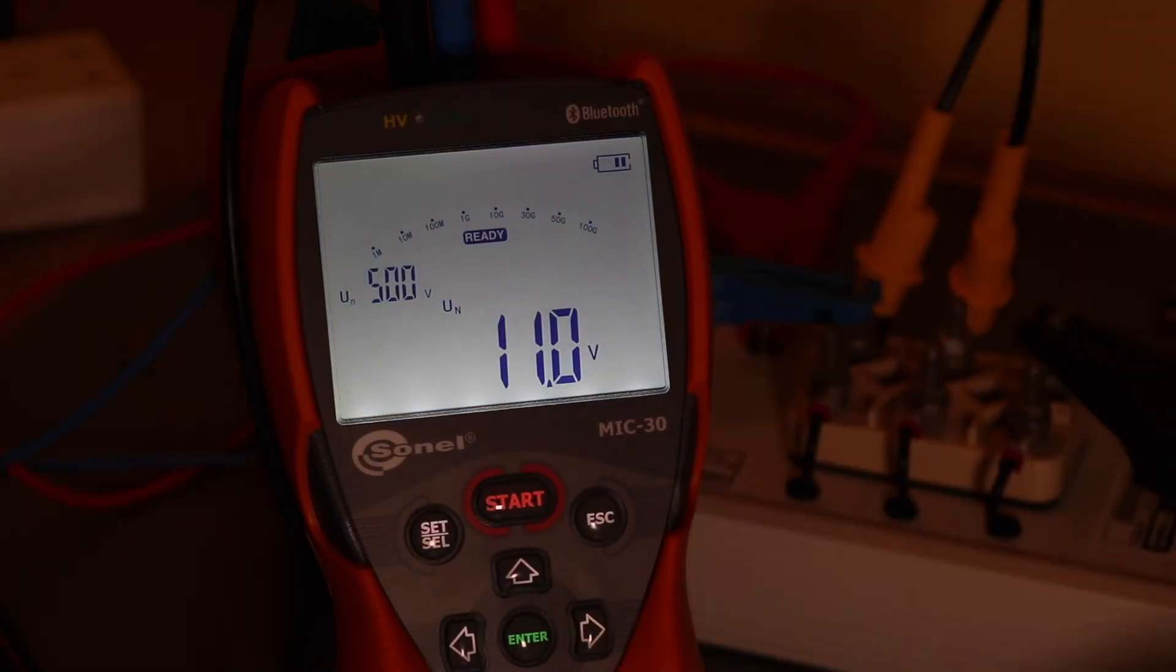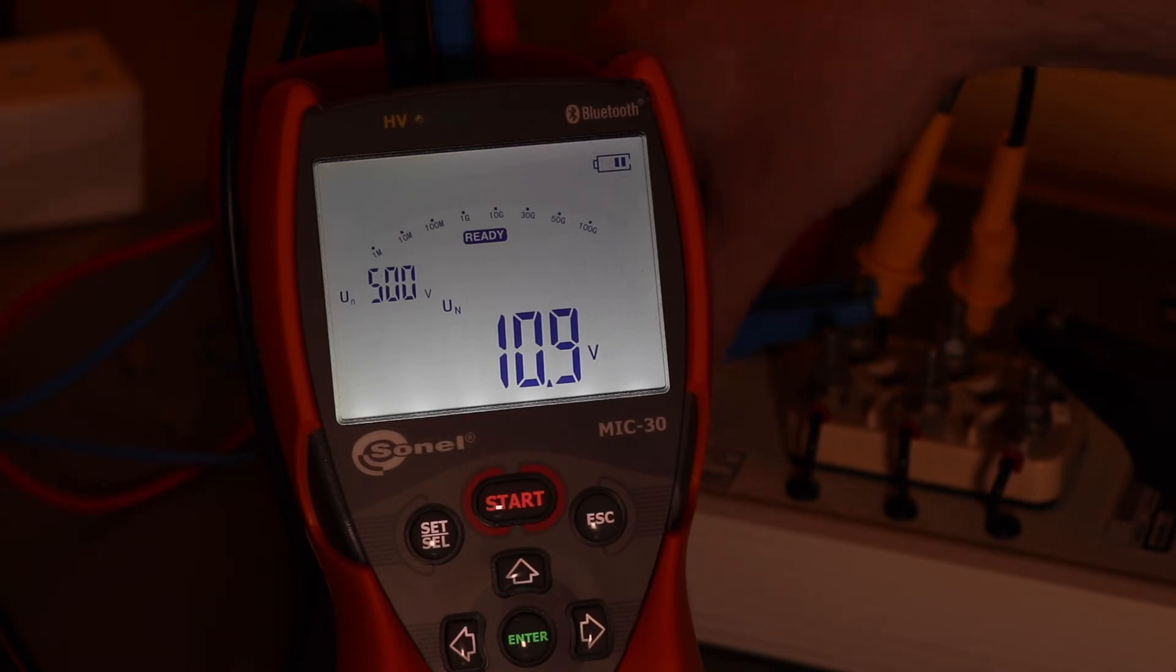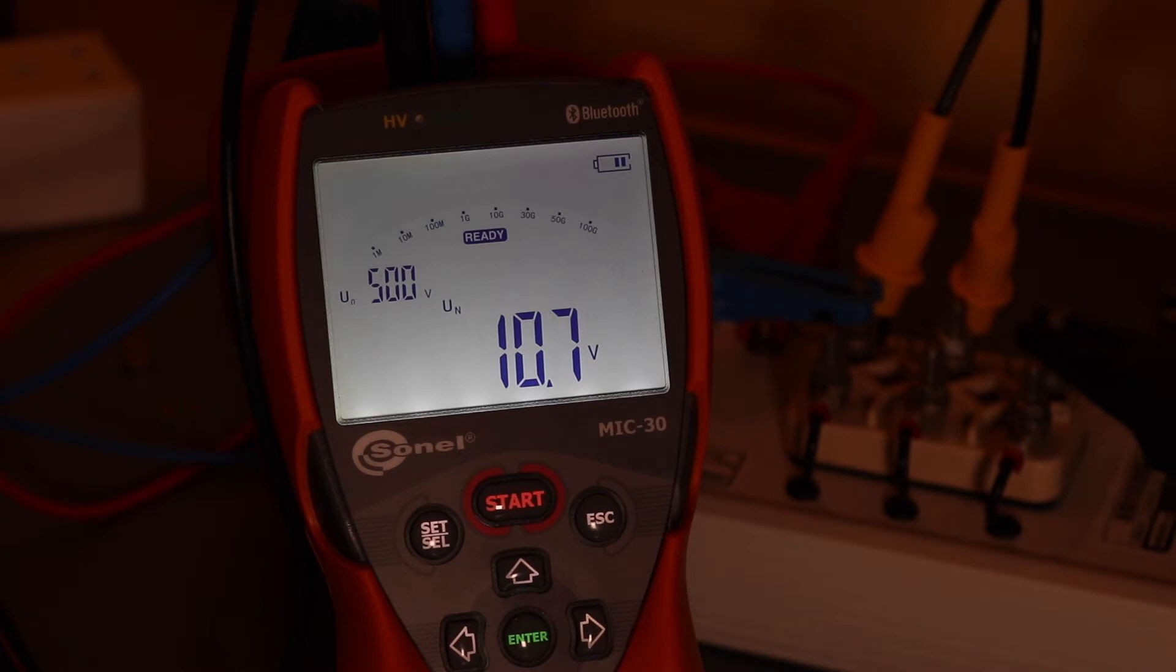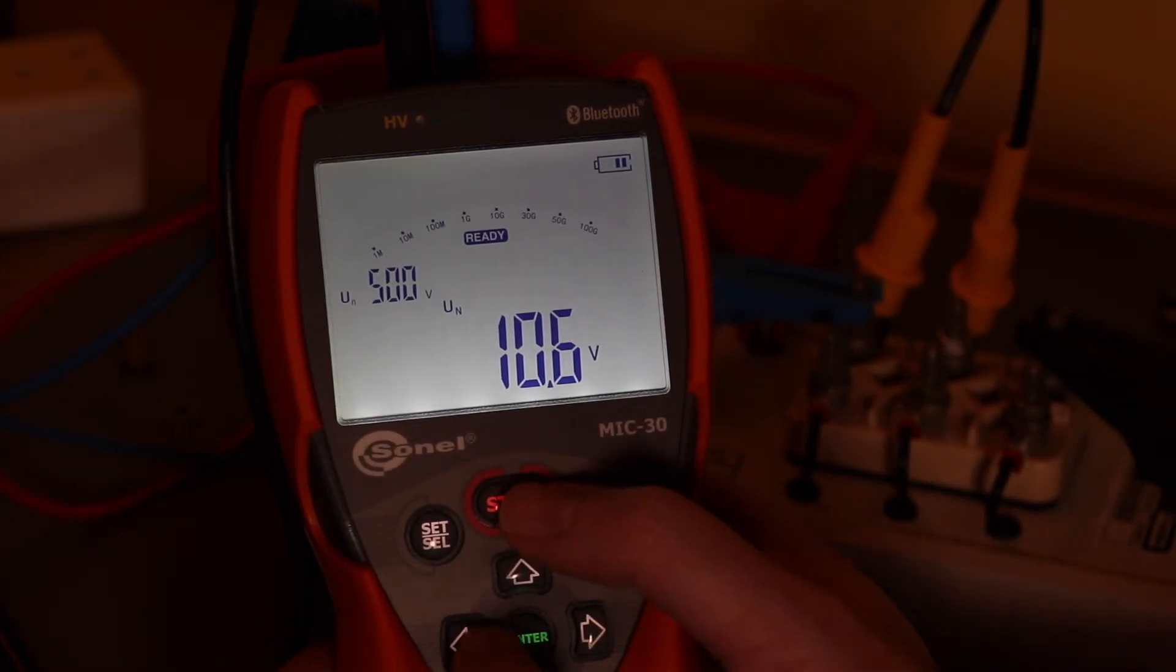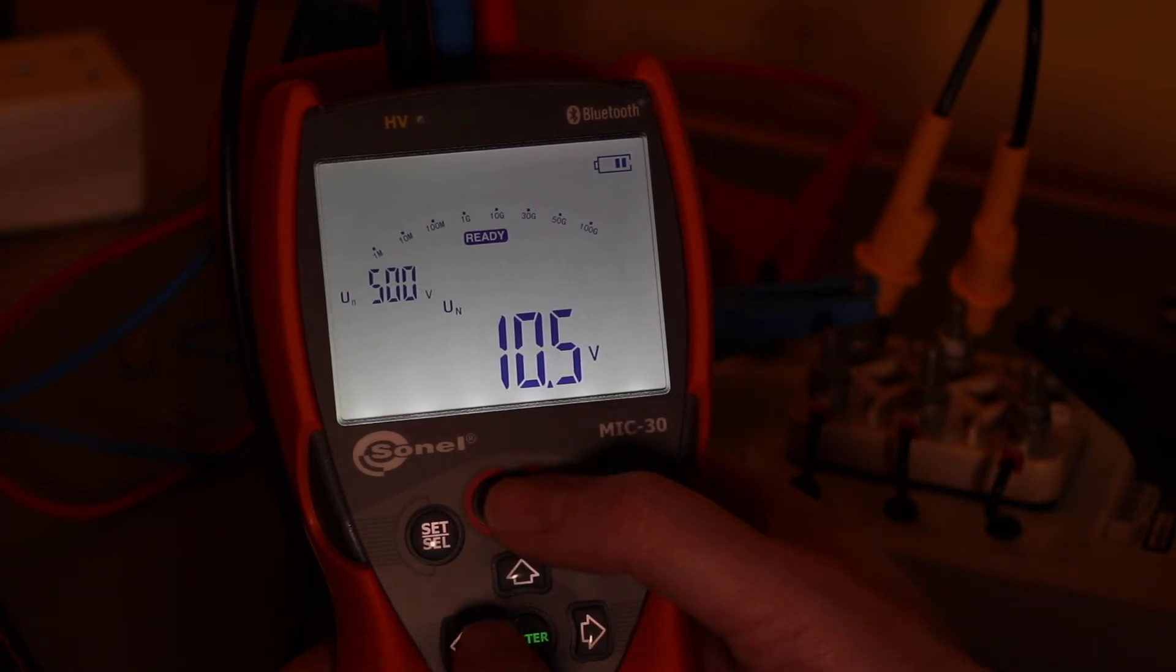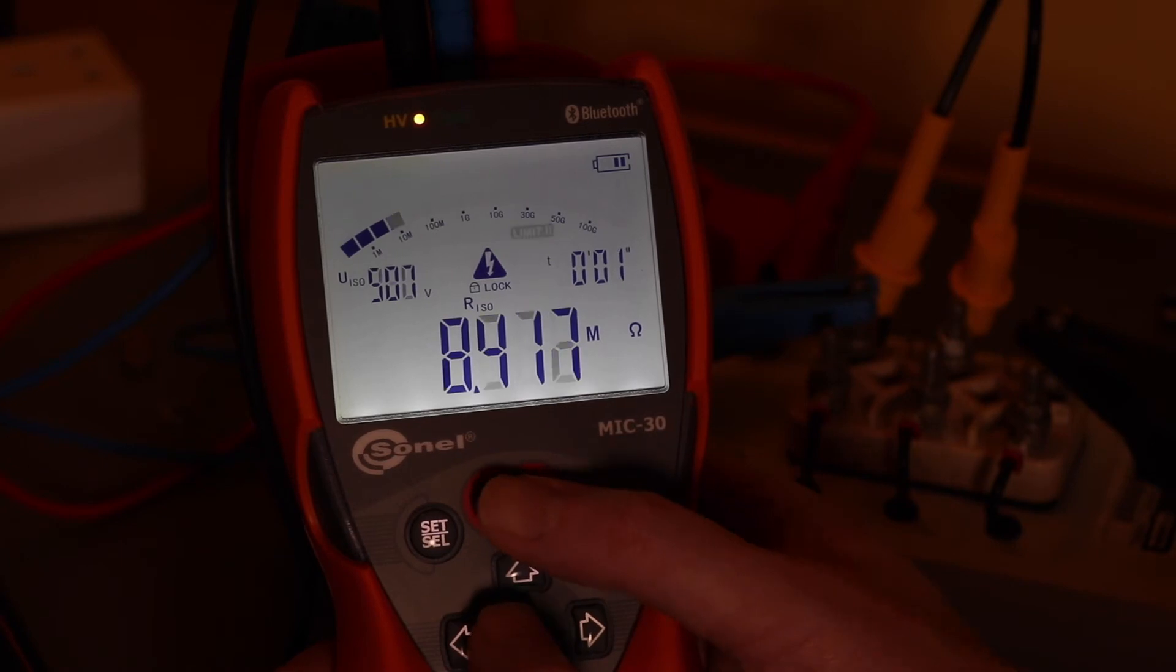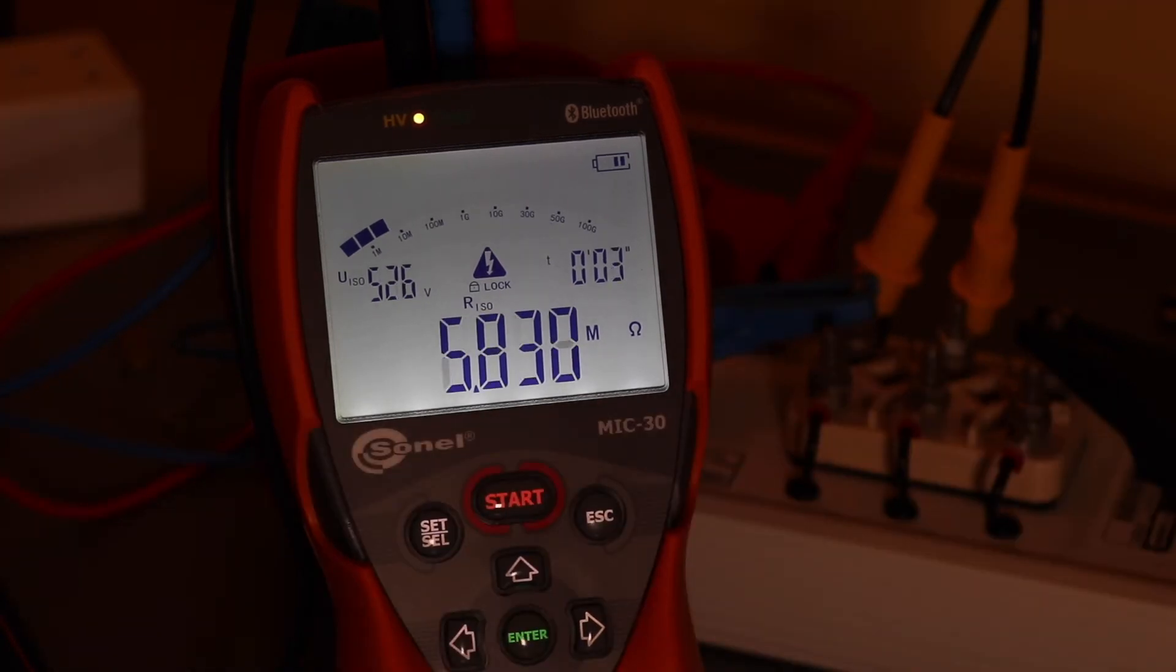This test setup now is using the guard terminal onto the two untested phases and just testing the U phase out. And we'll do this for another one minute test again. And hopefully you'll be able to see the difference in the results. So start here. Lock him on. And we wait for another minute.